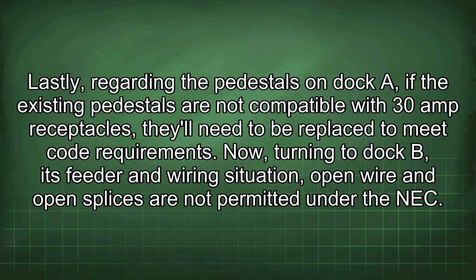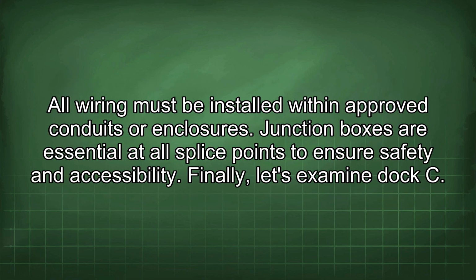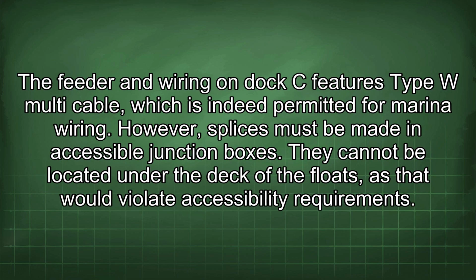Now turning to dock B, its feeder and wiring situation: open wire and open splices are not permitted under the NEC. All wiring must be installed within approved conduits or enclosures. Junction boxes are essential at all splice points to ensure safety and accessibility. Finally, let's examine dock C. The feeder and wiring on dock C features Type W multi-cable, which is indeed permitted for marina wiring. However, splices must be made in accessible junction boxes. They cannot be located under the deck of the floats, as that would violate accessibility requirements.